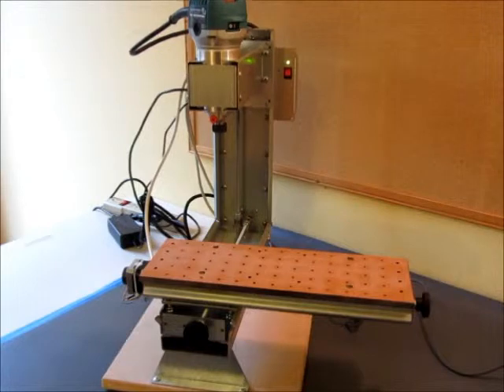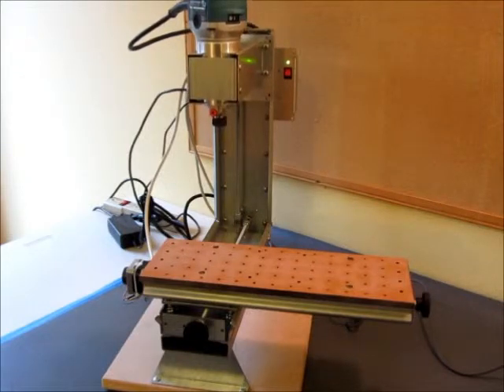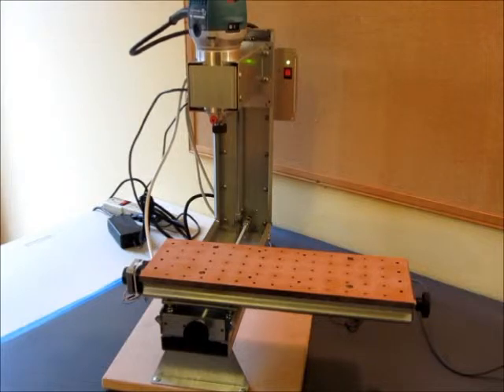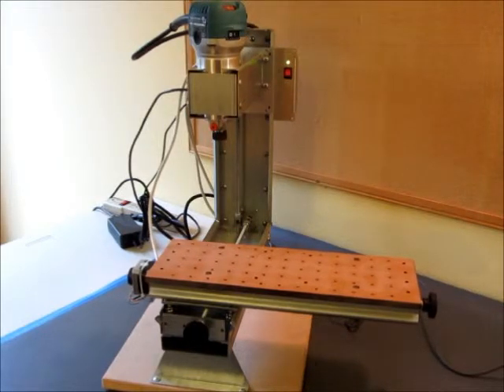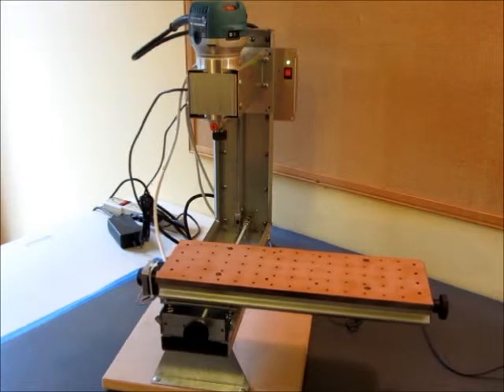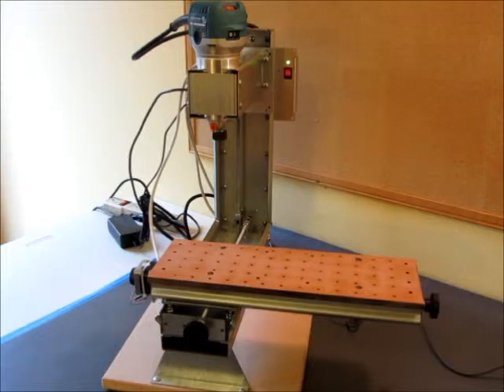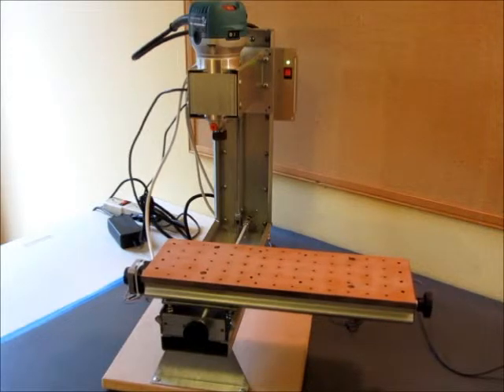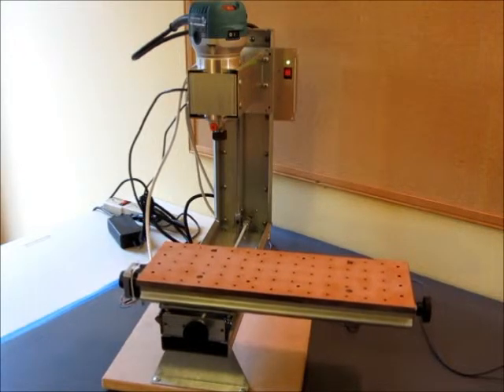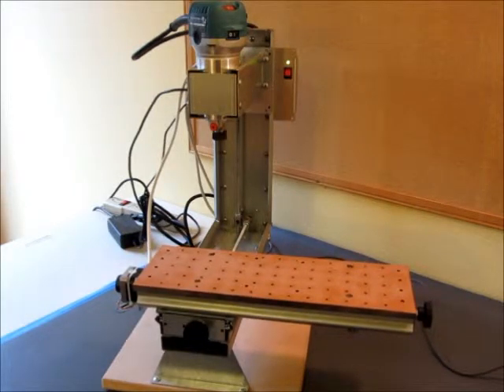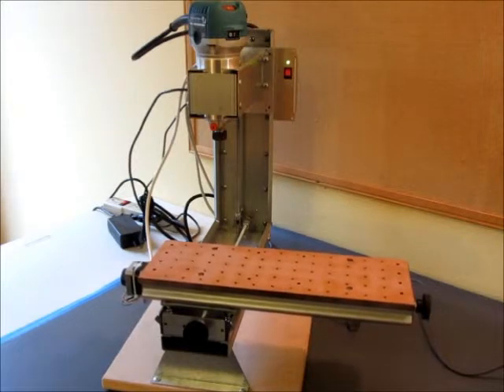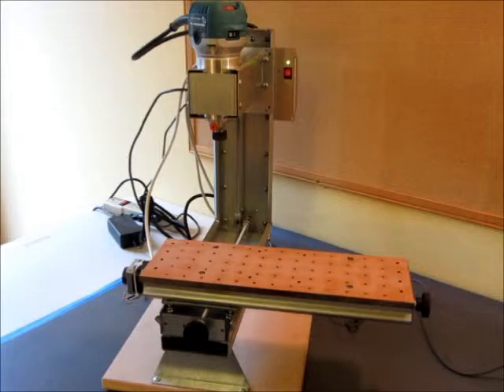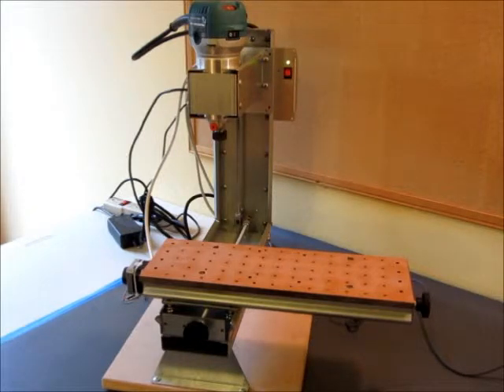The homing procedure moves each of the axes up against its hard stop. The Z axis in the positive direction, and then the X axis in the minus direction, and then finally the Y axis in the plus direction. After it hits each hard stop, it moves each axis back to within the normal operating range of the machine. Note that no separate limit switches are needed. It just uses the encoder information to tell when it's run into a hard stop.